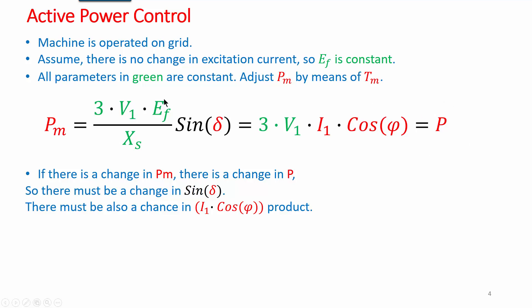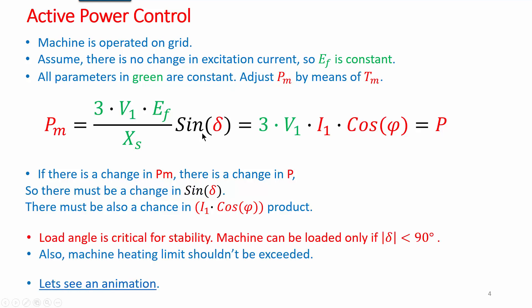Since the green-labeled terms (EF, V, Xs) are constant, any change in applied mechanical power PM must be compensated by a change in the sin δ term. On the right-hand side, the I cos φ term must change to compensate the power change. The loading angle δ is critical because machine stability requires δ less than 90 degrees. There is also a machine heating limit that must not be exceeded.